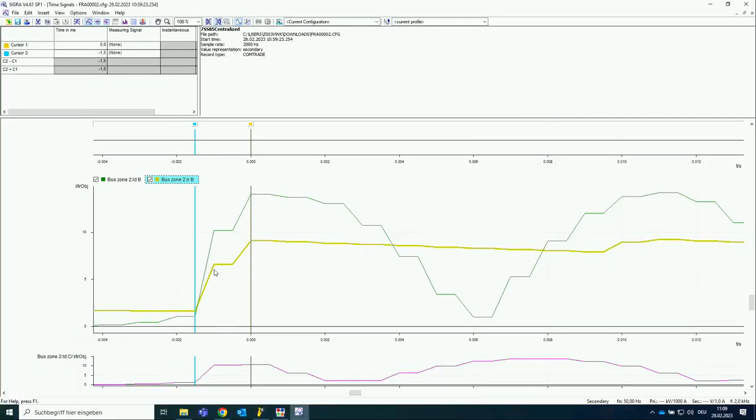And once again, if you remember, the one out of one algorithm has to be triggered by a jump of the stabilization current. And you see here, maybe once again, what are the numbers on the y-axis? I guess that's 10. Yes, that's 10. So you see here really a very big jump. From the blue line to the black line, it's 1.5 milliseconds. So that means we have a jump of the stabilizing current within 1.5 milliseconds of nearly 10 times the nominal current.